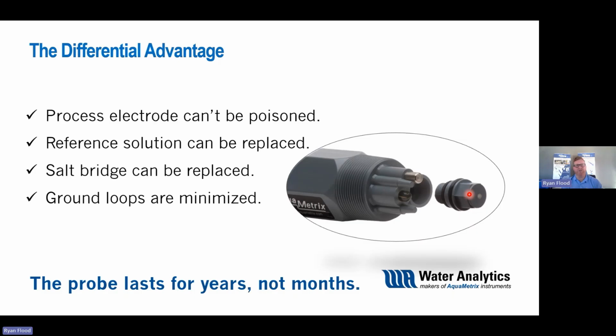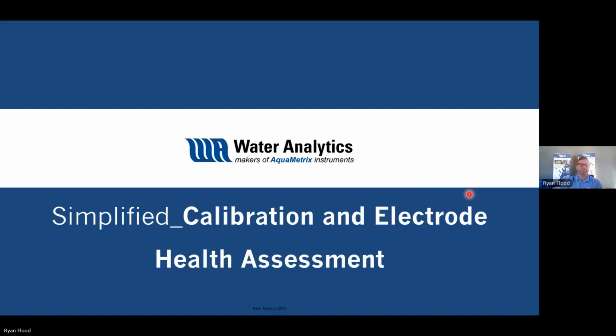But there's other advantages with the differential sensor, where it can also help eliminate some of the ground loops. And it's also going to give you a little bit more stability in some of your readings. But again, the real value with it is that sensor is going to last for years, not months, like some of the combination sensors out there.